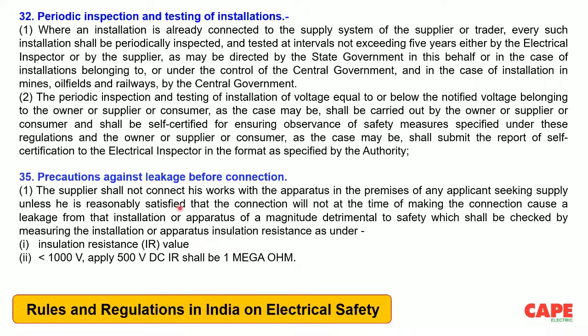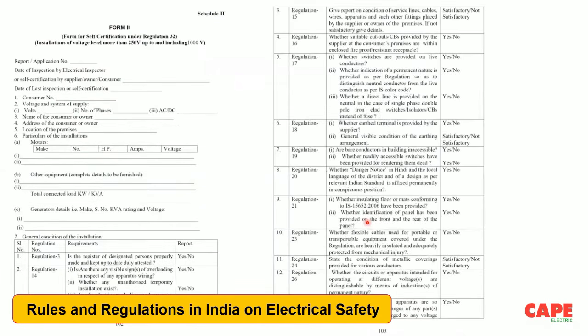Then precautions against leakage. I'm just showing you some of the regulations which are very much connected to safety in an electrical installation. Say, for example, I have put the new numbers. I think the earlier numbers were 30 and 33. Now the new numbers are 32 and 35. Regulation 32 talks about periodic inspection and testing once in 5 years, for example. Regulation 35 talks about precaution against leakage before connection. This regulation says that before you connect electricity to a consumer premise, you have to make an insulation resistance test, and the value shall be higher than 1 megohm. Unfortunately, these tests are nowadays not at all carried out, and this is one of the reasons for accidents. Also, the regulation explains the formats. The reason for showing these formats is that probably in future, people will start doing the electrical safety audit as per this particular format.